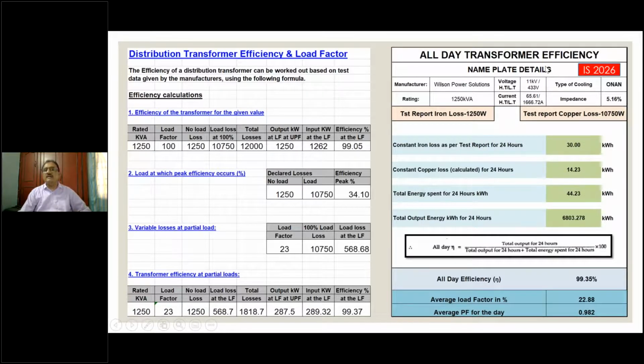We also have another format with which we calculate all-day transformer efficiency. This is very important. For any facility you go to for auditing, if you take 24-hour data and also use this format to arrive at the all-day efficiency, you can notice here, based on the data available, the all-day efficiency is 99.35%. This is with one instantaneous value where we found 23%. This is a dynamic value where the average load factor was 22.88, fine-tuned. The average power factor for the day was 0.982, and the all-day efficiency of the transformer is 99.35%. I do not know if anybody else is doing this exercise when they are doing an audit, but we definitely do this, and we take pride in telling you that we are one of the leading exponents in the country to use this format for measuring the all-day efficiency of the transformer.